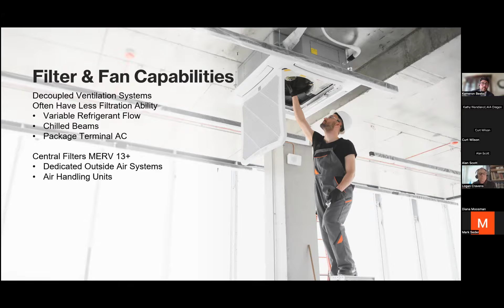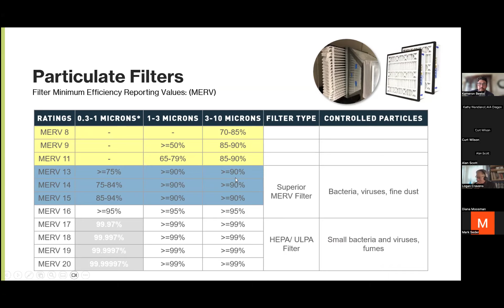You'll see in California, there's OSHPD standards or HCAI standards that require MERV 14 or MERV 15 in some instances. But a lot of those smaller units that I was talking about, those zone level decoupled systems, they tend to see only a MERV 8 for those applications. And again, we're looking at PM 2.5, which is the center column right here. We're trying to get rid of those as well as the 3 to 10 micron particulates. So you can see that MERV 13 does better than 90% for those particulates.